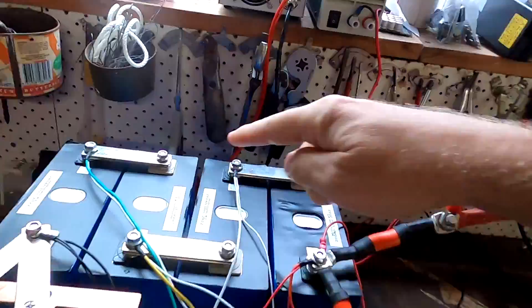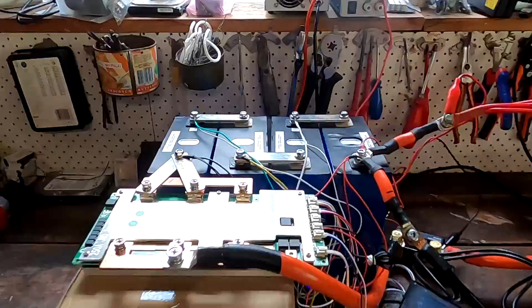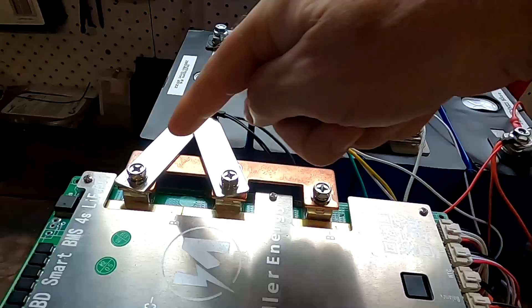What I'm using here in the battery shelf is totally sufficient. There's no heat building up at 100 amps or anything. But today we want to go 200 amps at least, hence the double bus bar, 6 Newton meters of torque.